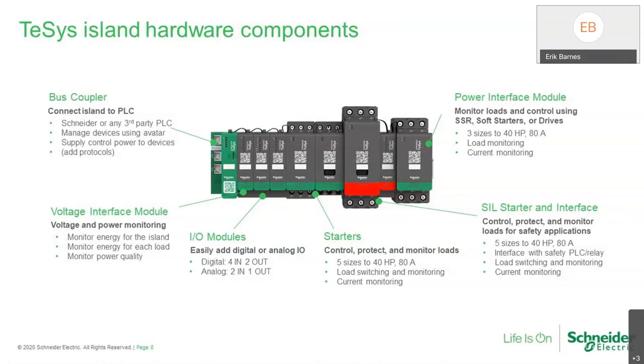So we have that as kind of the brains of the operation. We have an optional voltage interface module, which allows you to detect voltage, so you can monitor for voltage anomalies. Once you add this module, you'll also be able to detect energy and power consumption. And you only need one module for the whole island, no matter how many starters you have. We have optional I/O modules, so there's a digital and an analog module, and you can add as many modules as you like within a limit of the island. And so you can fit that to your particular application.